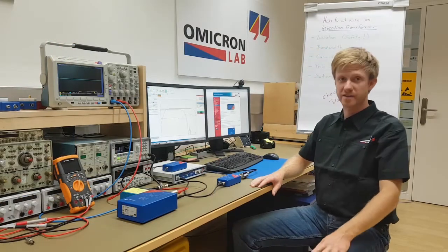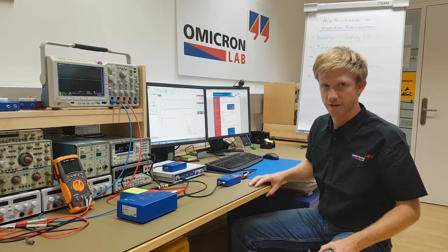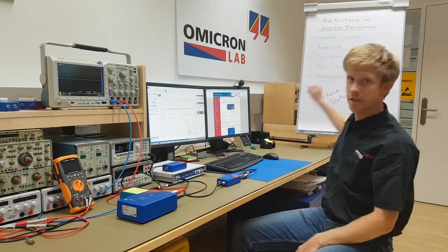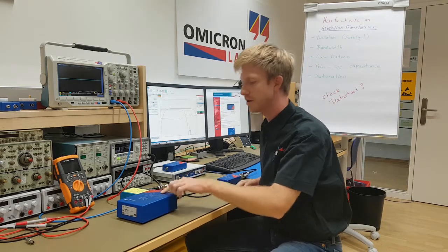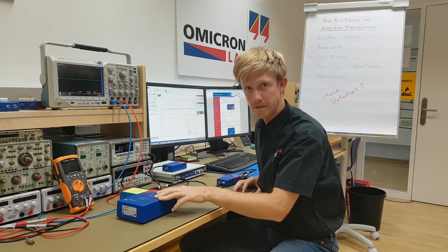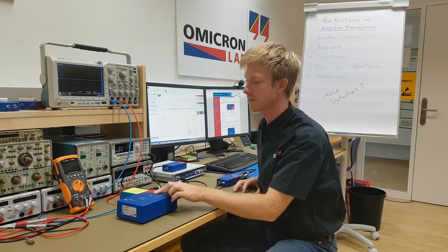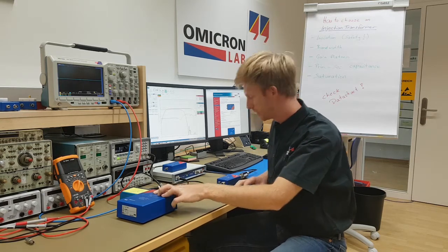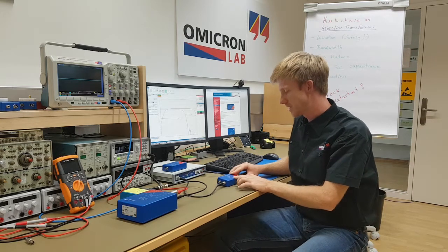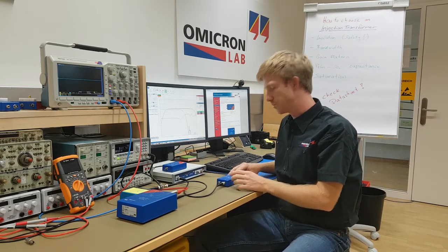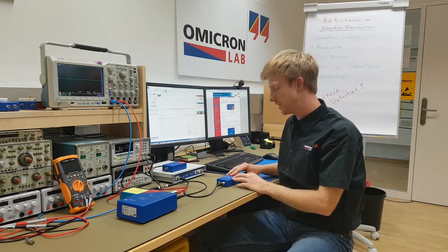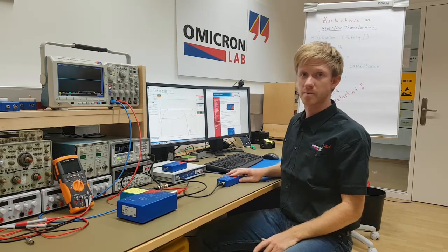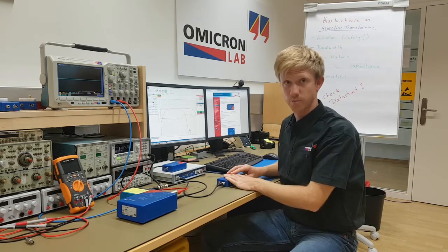Okay, so now let's have a look at these parameters in real life. The first thing, isolation, and that's about safety. If we look at our products, here you always find a marking that specifies the isolation, and here it says 600 volts category 2 on the B-WIT 100 as well, 600 volts category 2 between primary and secondary isolation. This means that even if a transient from the line comes in, this isolation will not break.